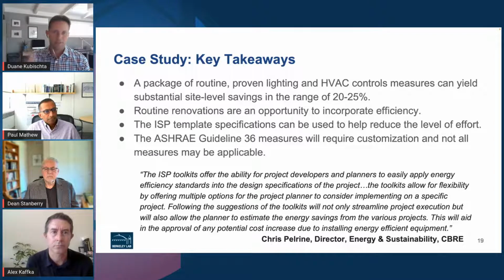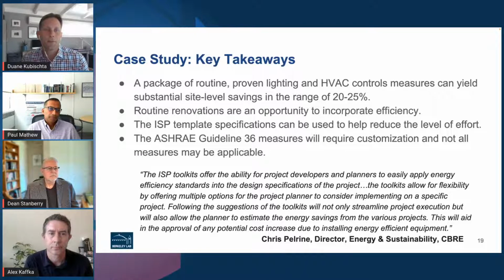It was just a slam dunk. Yes, we'll do the duct static pressure reset. We already have the VFD. We already have a sensor. Let's just turn that on with some controls. So it was a great win to see that. Couple other points here.